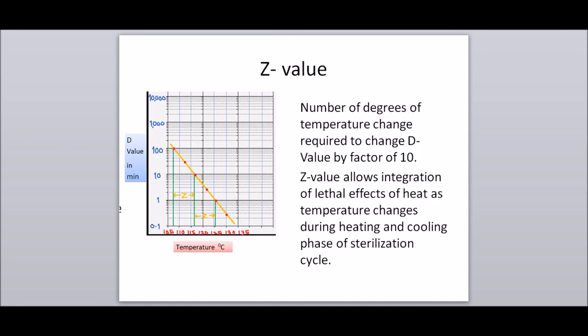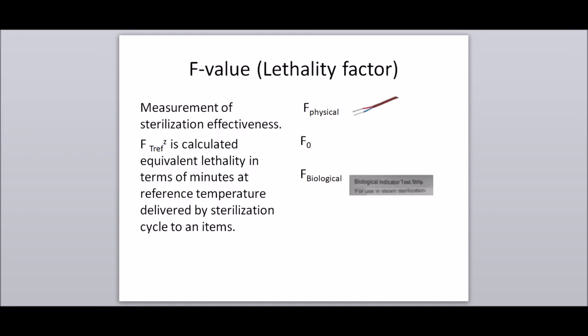Z value: the number of degrees of temperature change required to change the D value by a factor of 10. It is the integration of the lethal effects of heat as temperature changes during the heating and cooling phases of a sterilization cycle. F value, or lethality factor: a measurement of sterilization effectiveness. F subscript T-reference superscript Z is the calculated equivalent lethality in minutes at a reference temperature, delivered by a sterilization cycle to an item.